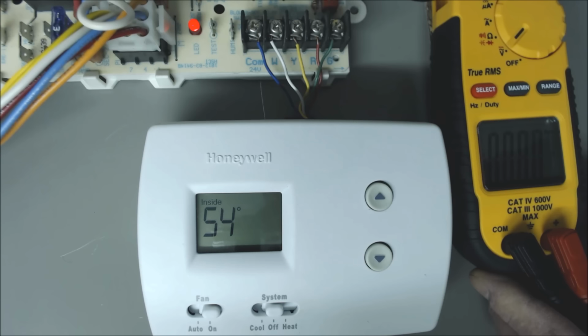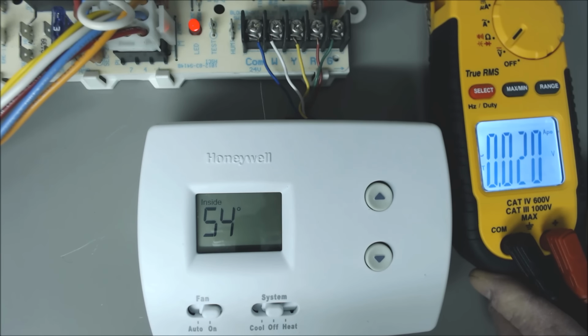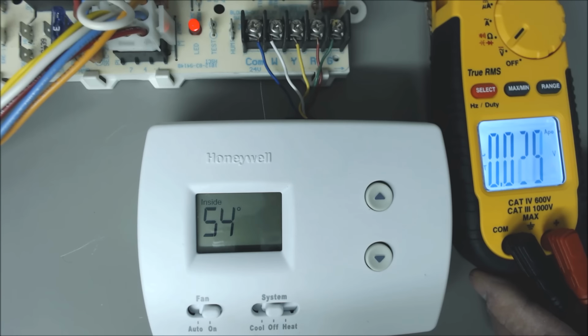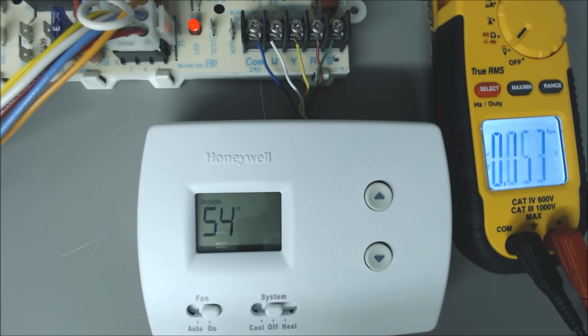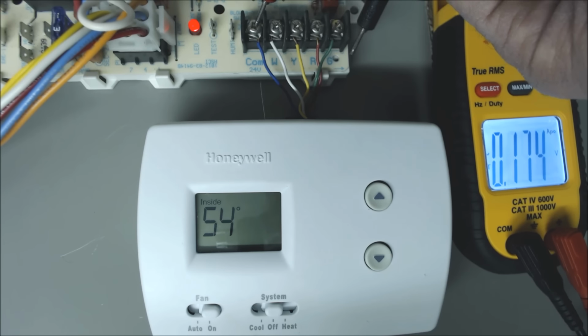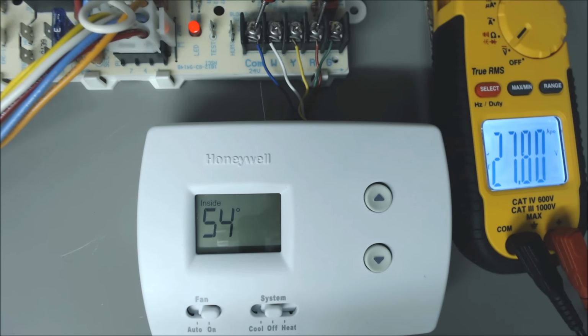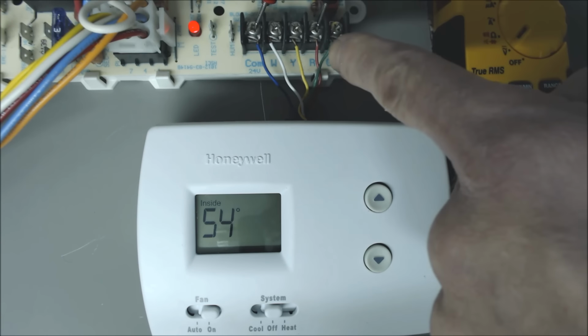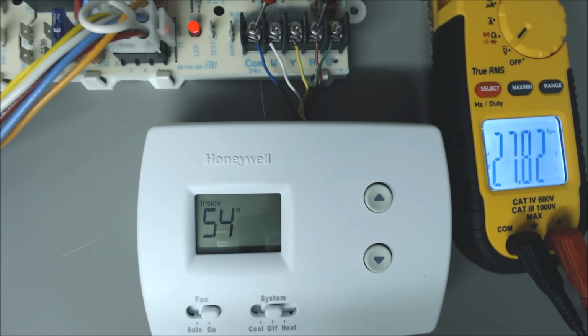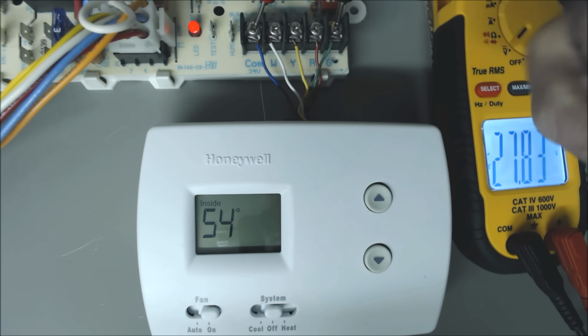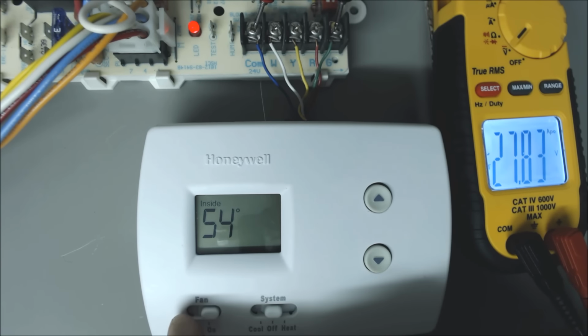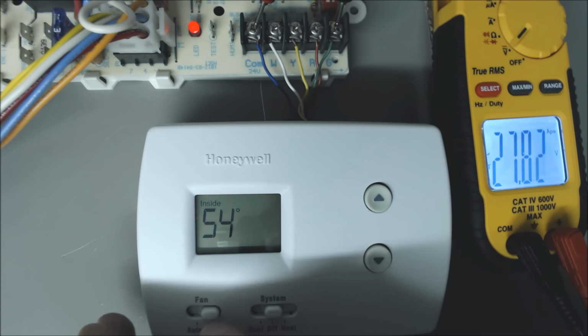We're going to turn this multimeter on to volts AC. We're going to turn the light on. This is a UEI DL479, same basic multimeter as a DL469, except this one happens to have a temperature sensor as well. So if we were going to check for voltage, we could go between common and R, and you have 27 volts because you have a hot wire R and a common wire C. Right now we're going to read 27 volts here on the G because we're actually connecting the R and the G inside the thermostat to turn the fan on.